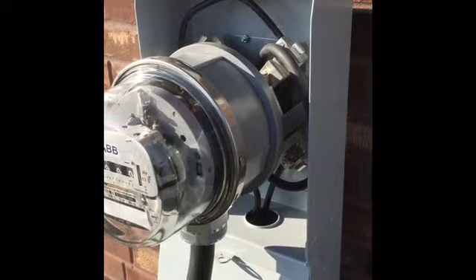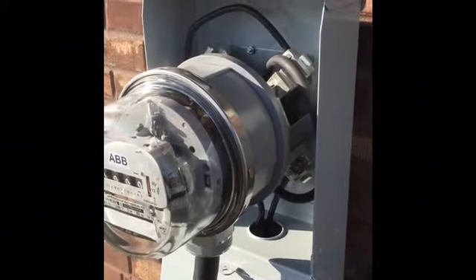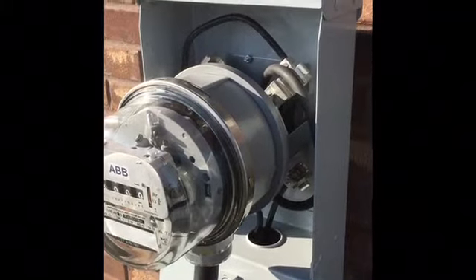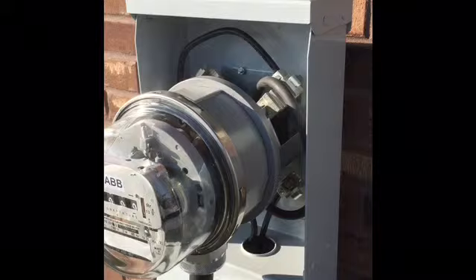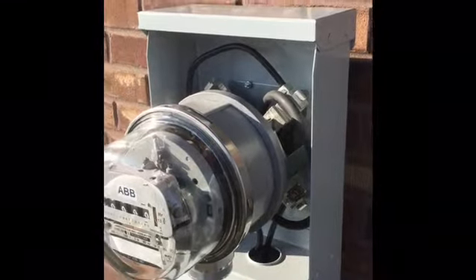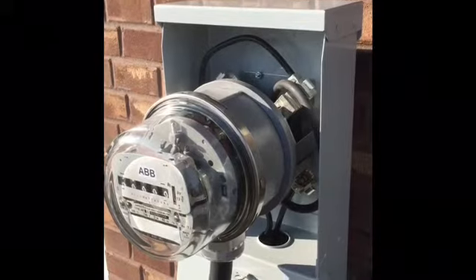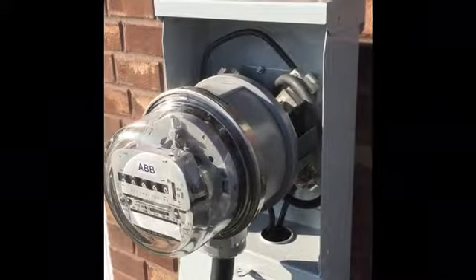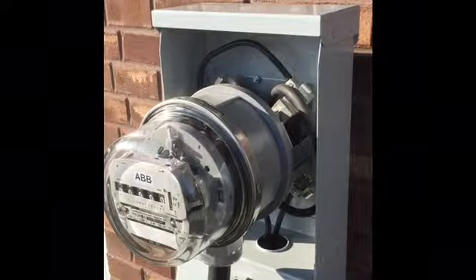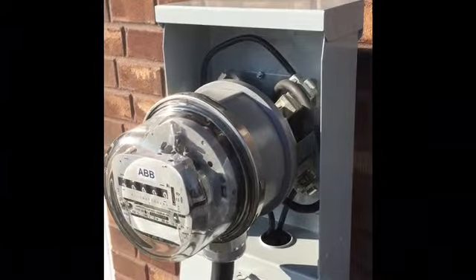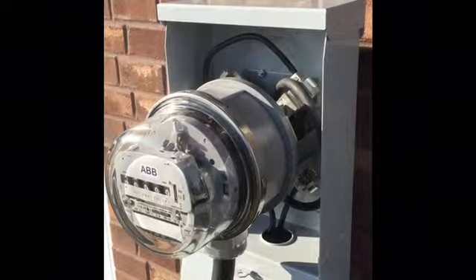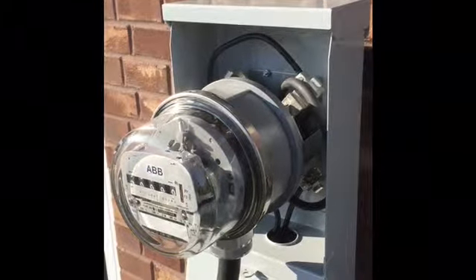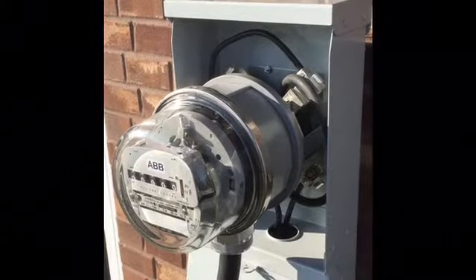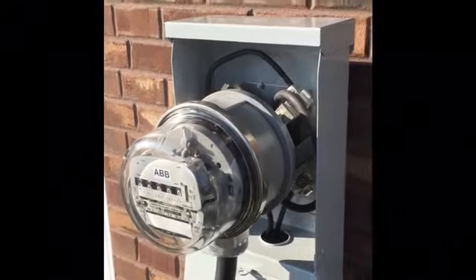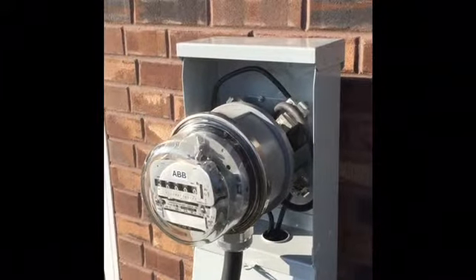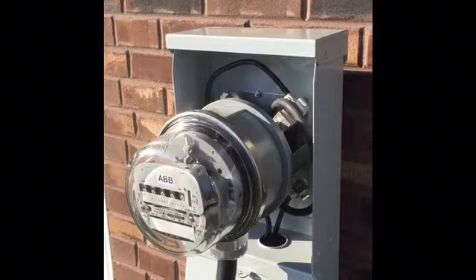Okay, after we turn our customer's breaker on, we want to come out and test the amps on the neutral pigtail, and then also test the voltage across the line connectors on the meter socket. So for a 15 kVA unit, we want to make sure the amps on the neutral are below 125 amps. And then for a 25 kVA unit, we want to make sure the amps on the neutral are below 208 amps. So that's crucial, because if we exceed that, then we're exceeding the rating of the transformer and could potentially get in a situation where we're overloading the system.